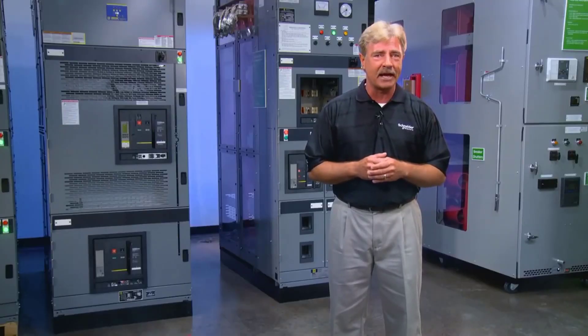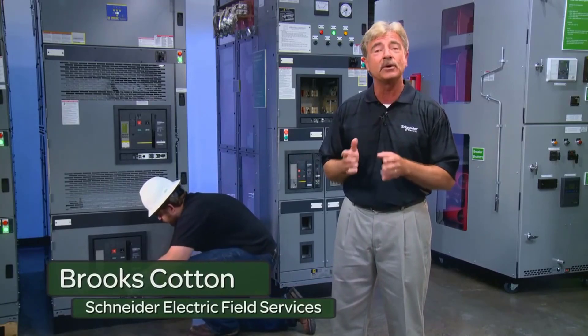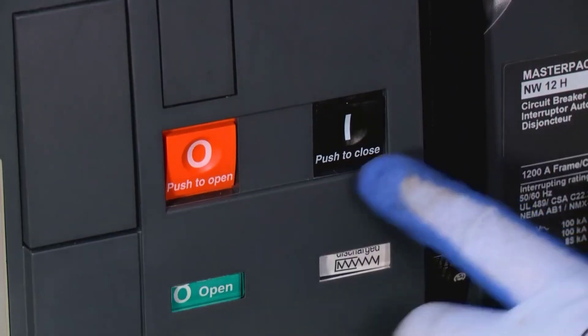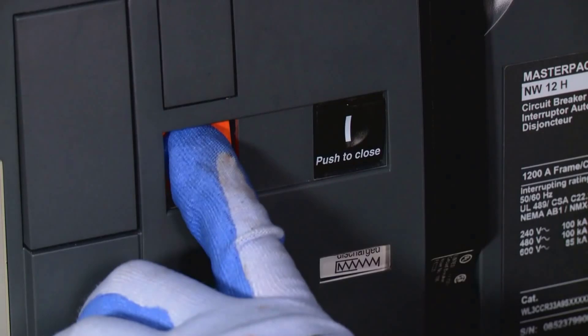Let's walk through the process of racking out the MasterPact breaker. We're with Schneider Electric Field Services to show us how. First, make sure the breaker is turned on. Press the press-to-close button to discharge the spring, then press the press-to-open button to open the contact.